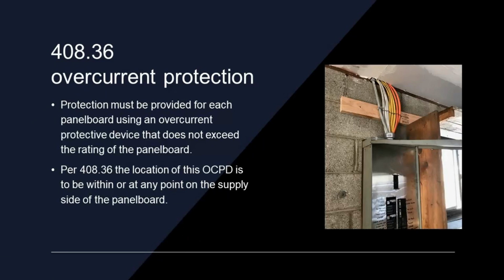Look at that cover. That looks homemade, doesn't it? So per 408.36, the location of this overcurrent protection device is to be within or at any point on the supply side of the panel board. Okay, so we are required to have overcurrent protection for a panel board somewhere, right? I mean, we're going to either have it at the main, we're going to have it at the panel board, maybe both.